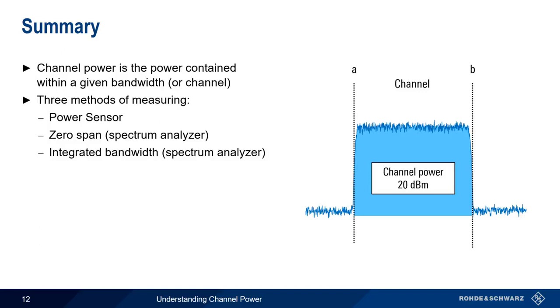Since channel power is a power measurement, our detector type should always be set to RMS when we measure channel power with a spectrum analyzer. This concludes our presentation, Understanding Channel Power.